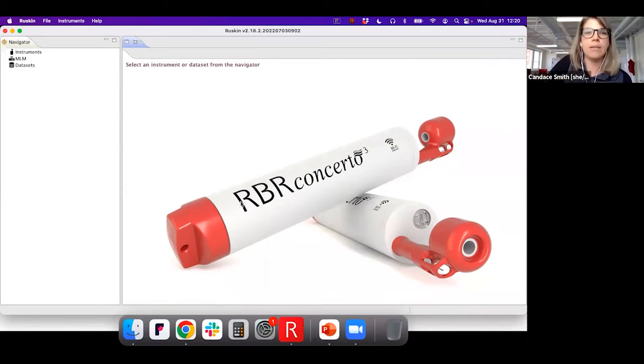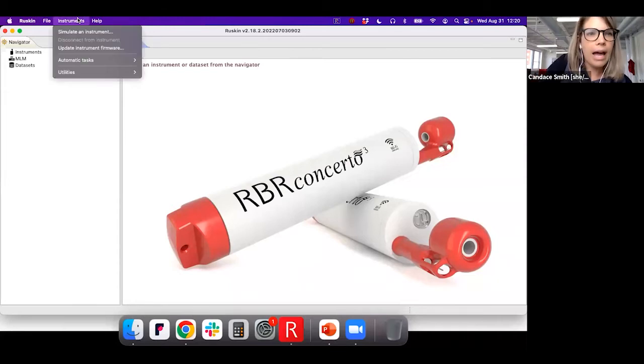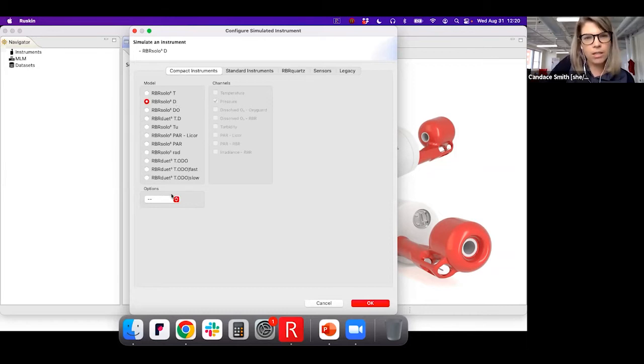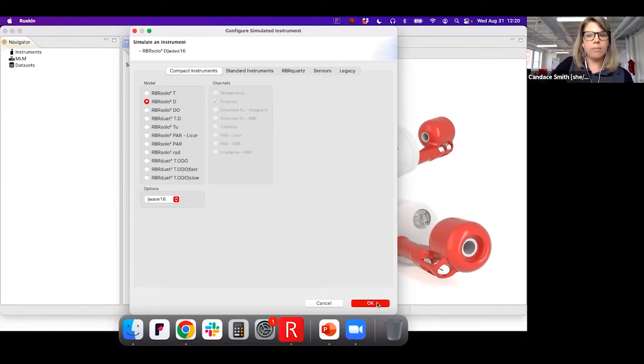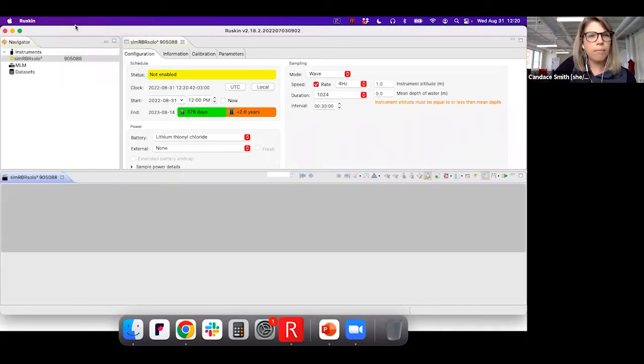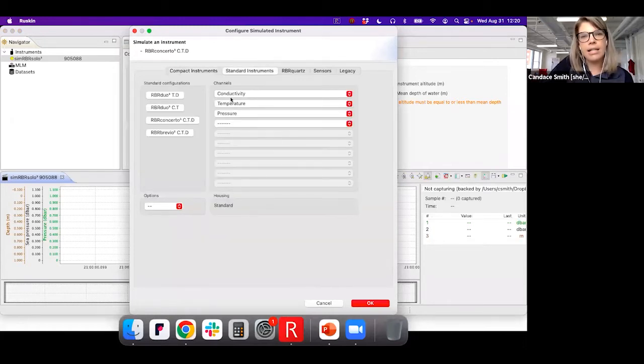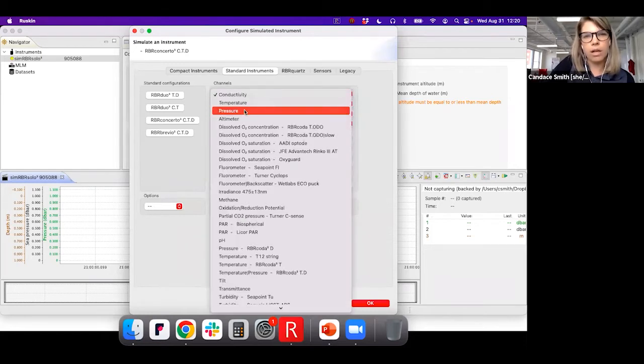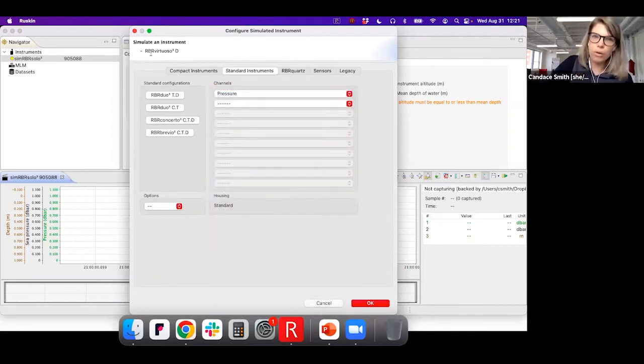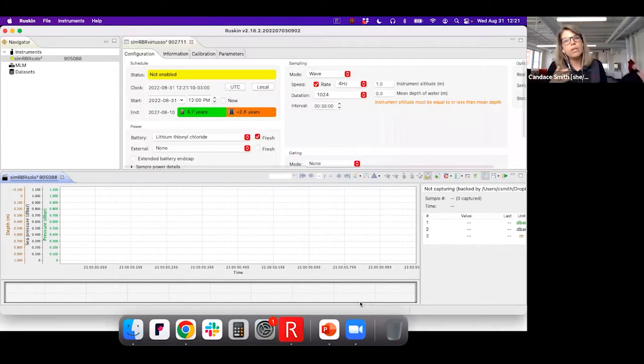I can simulate these instruments in Ruskin without plugging them in. If I change the battery chemistry, it tells me how long an alkaline versus a lithium battery will last. Go to Instruments > Simulate an Instrument, select the Compact Instruments panel, go down to Solo-D, and under Options click Wave 16. I've now generated an RBR Solo-D Wave 16 — my favorite instrument. I'll also simulate a Concerto: Simulate an Instrument, go to the standard instruments panel, click the pressure channel, and enable the Wave 16 feature.